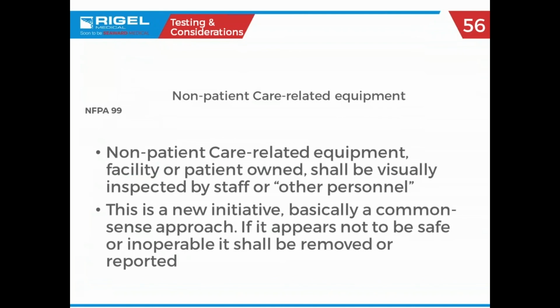This was also a fairly new change, although it's better documented now. Technically, if your patient brought in a radio or a computer or something else, you were supposed to do electrical safety on it because it's going into the patient environment. And technically, the biomed was the one who was supposed to do that. NFPA 99 now says anybody in hospital personnel can look at it and do a visual. Is it safe? And you don't have to test it.